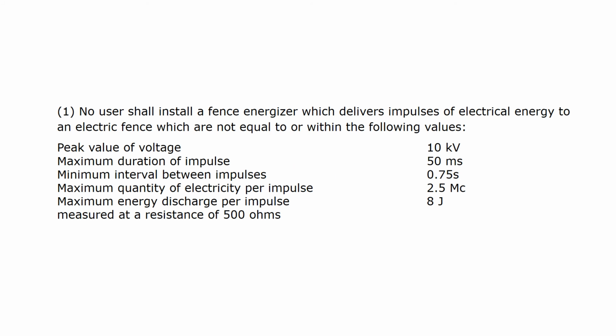Electric fences. No user shall install a fence energizer which delivers impulses of electrical energy to an electrical fence which are not equal to or within the following values. Peak value of voltage: 10 kilovolts. Maximum duration of impulse: 50 milliseconds. Minimum interval between impulses: 0.75 seconds. Maximum quantity of electricity per impulse: 2.5 mC. Maximum energy discharge per impulse is 8 joules measured at a resistance of 500 ohms.